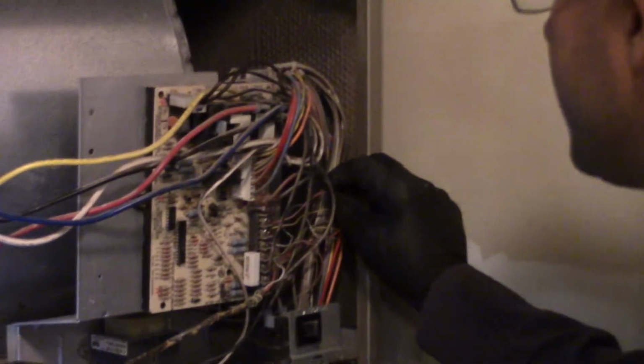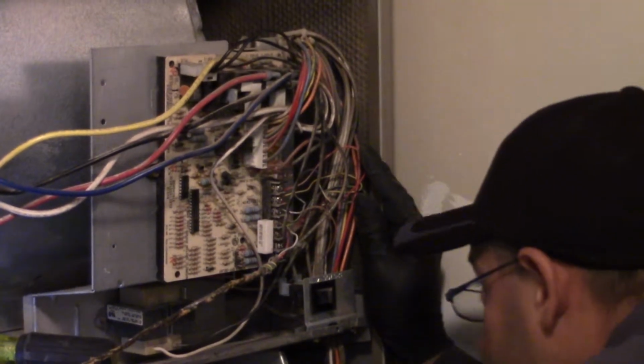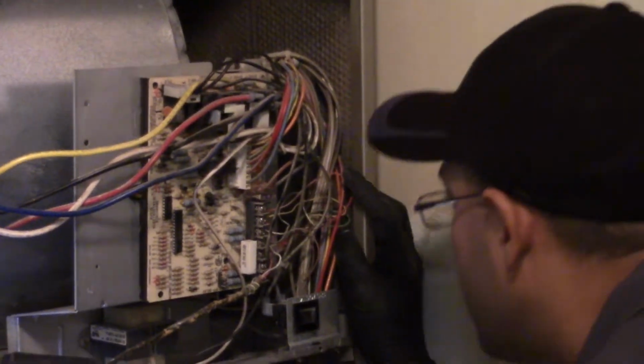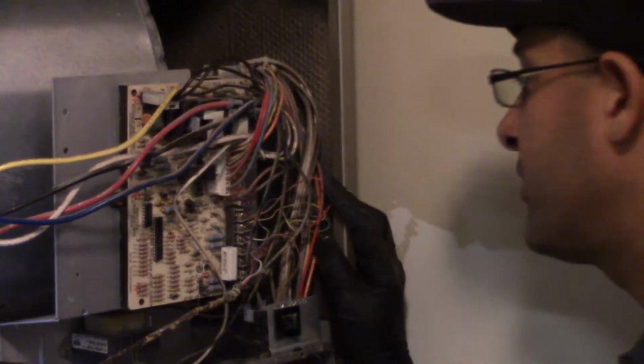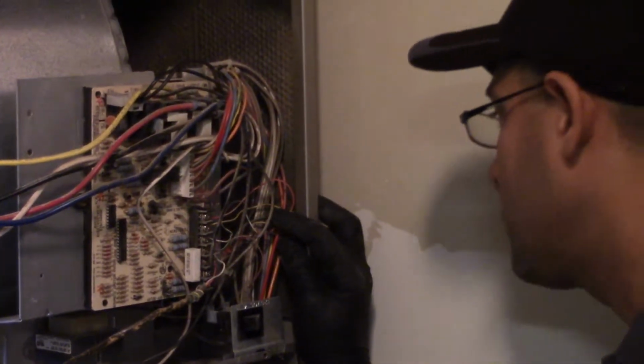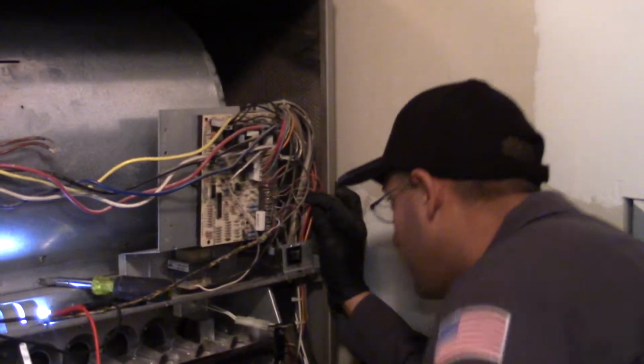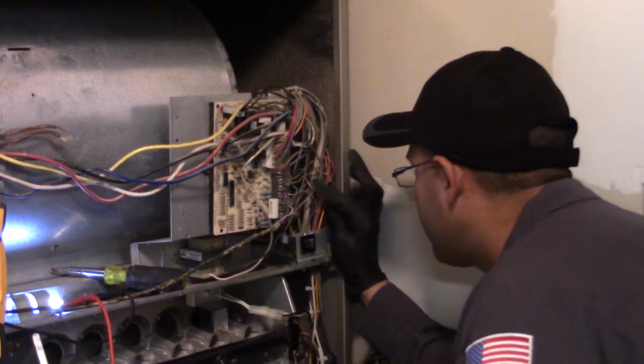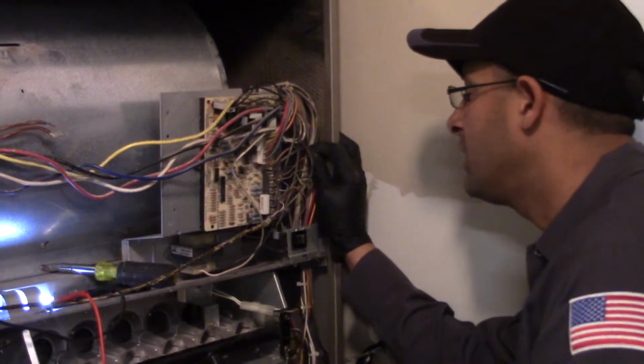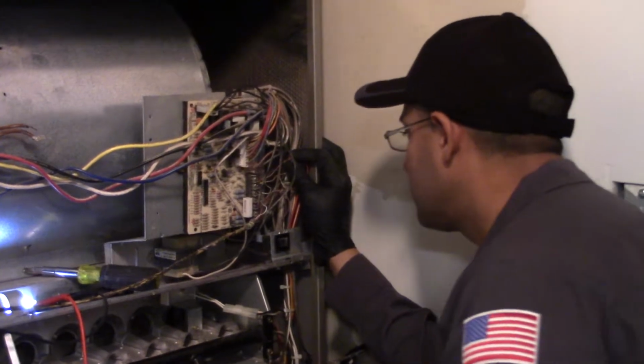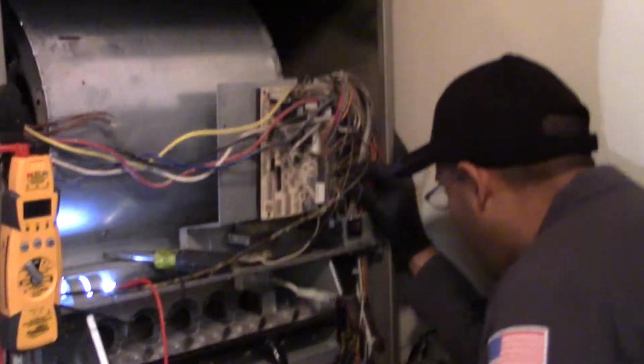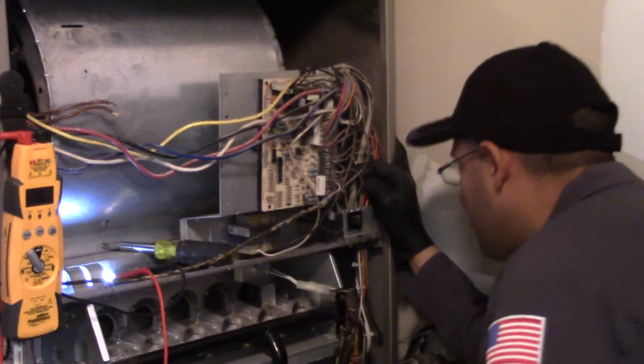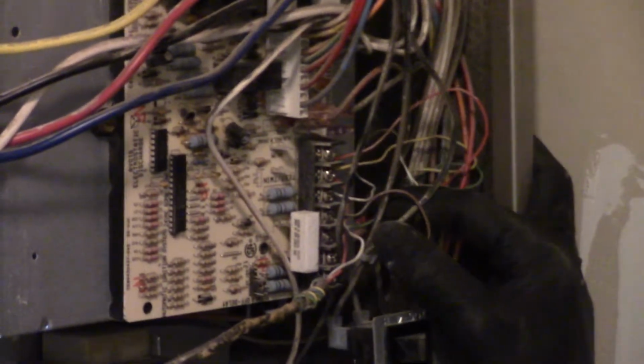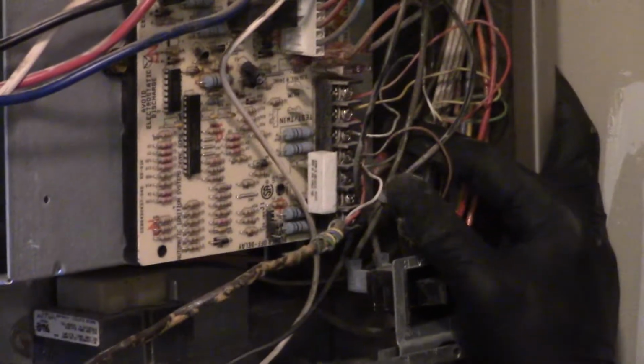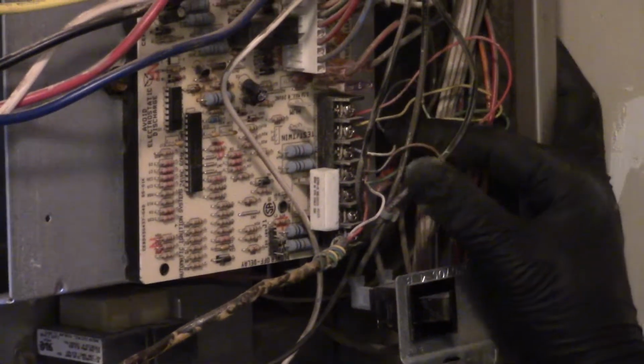And then we have our other thermostat wires. On this one we've got the thermostat Y from the thermostat that connects in the same terminal block for the AC, and then we have our power, which is R, and that's going to the thermostat as well. And then we have our G wire, which is our fan, and that's going to the thermostat as well. And we have our W wire, which is always for heat, and that's going to the thermostat as well.